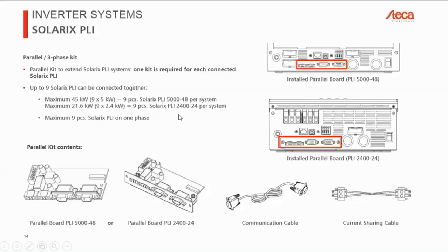There's one small note. I've mentioned before that the switchover time from the grid or from the AC source to the off-grid mode is 10 milliseconds for a single device. If you're using more than one device, then this switchover time can be longer, particularly in a 3-phase system. The absolute maximum is 50 milliseconds as a switchover time, even if you're using 9 3-phase devices. So just keep in mind that the switchover time will be slightly longer if you're using the system with several SOLARIX PLI inverters connected together.